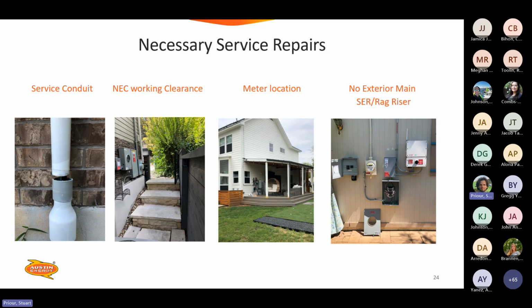And then lastly, we have the no exterior main, or there's a rag riser or a service entrance cable that is outdated and not approved by Austin Energy. So you can see in there, that's the revenue meter there that's painted the color of the house, but it doesn't go to an exterior disconnect. It goes into the house, which is where its disconnect is. So that's something that we'll need to get repaired before we can do a solar inspection.